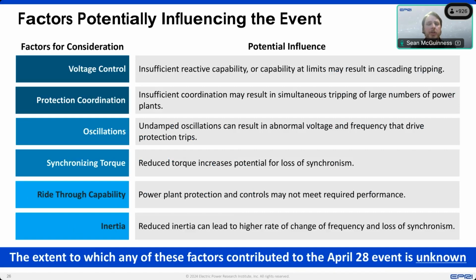We've seen from the 2021 event that voltage control played a substantial role in the event. So if you're in a grid which is undergoing rapid changes in energy sources, it's very important to consider voltage controls, both static and dynamic, ensuring that there's sufficient reactive power capability and that you're leveraging the available capabilities as well. And that you're aware of which reactive power sources you're using, which ones are at their limits, and any issues that may arise. How sensitive is your grid, or how close is your grid to initiating cascade tripping? How sensitive are you to managing elevated voltage conditions on your grid? And how many devices or resources tripping would it take to begin initiating cascade tripping?